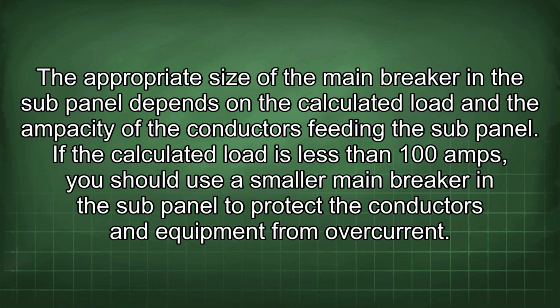The appropriate size of the main breaker in the sub-panel depends on the calculated load and the ampacity of the conductors feeding the sub-panel. If the calculated load is less than 100 amps, you should use a smaller main breaker in the sub-panel to protect the conductors and equipment from overcurrent.